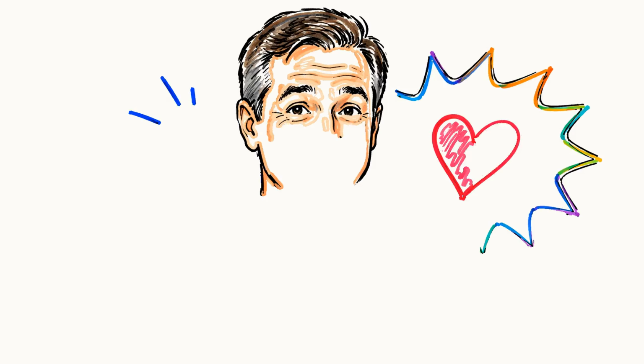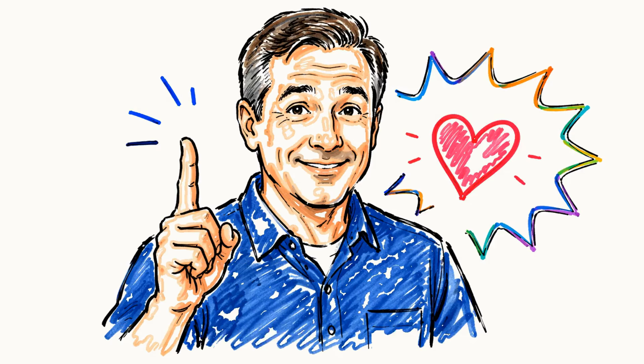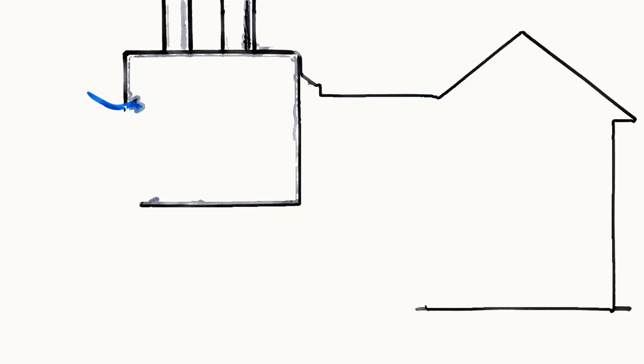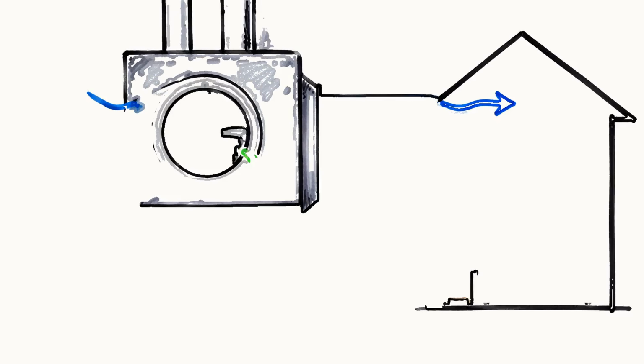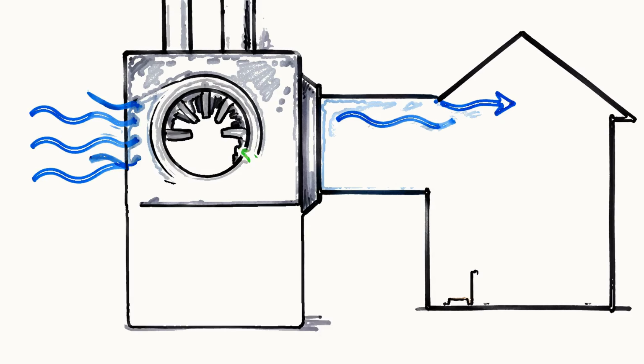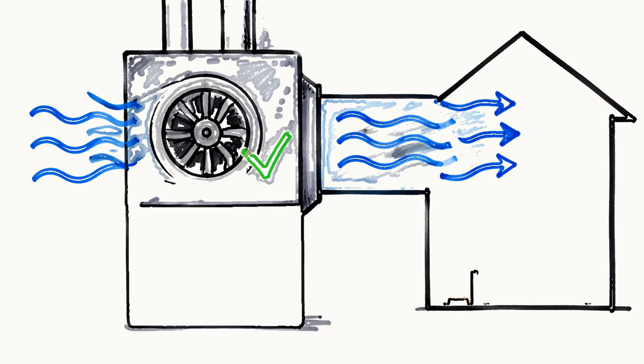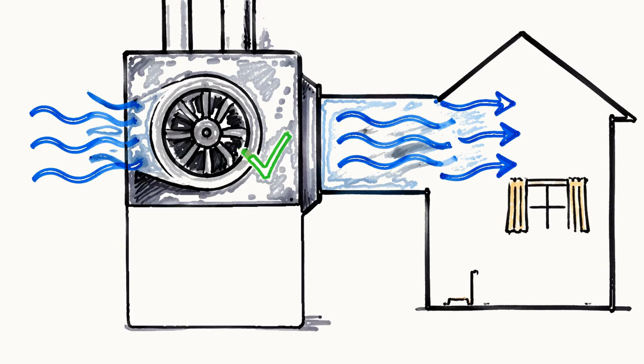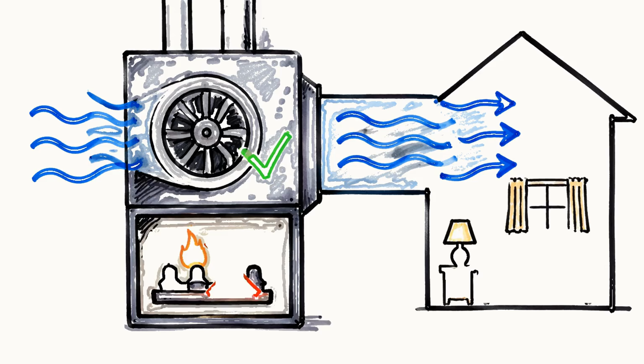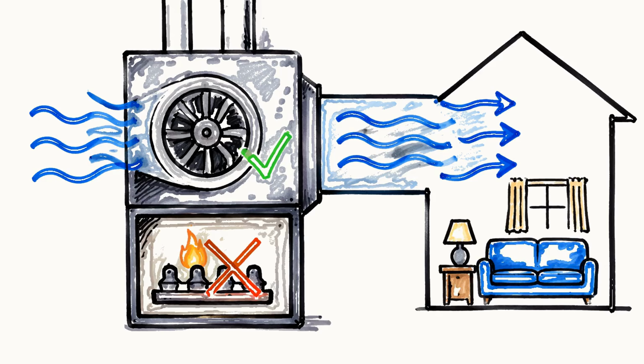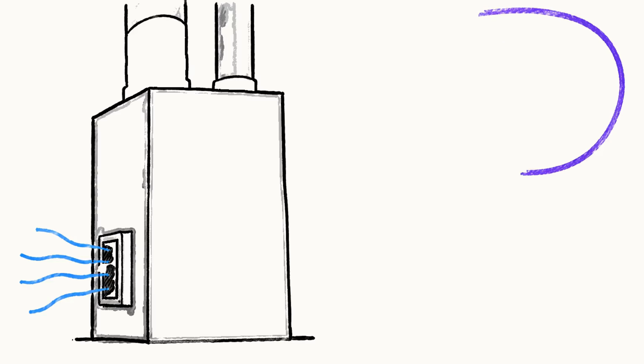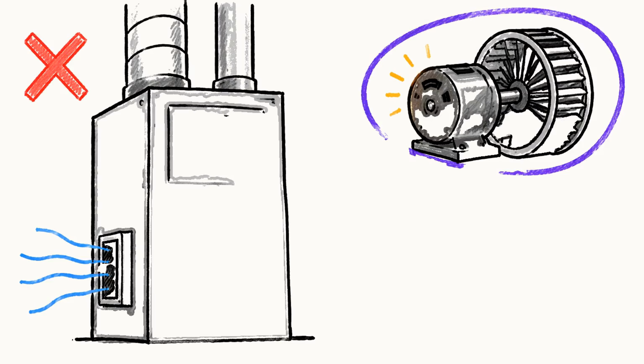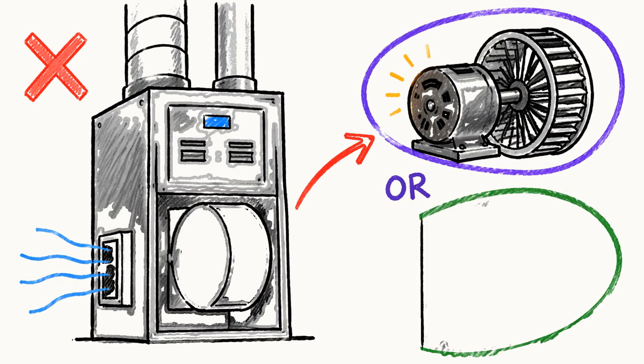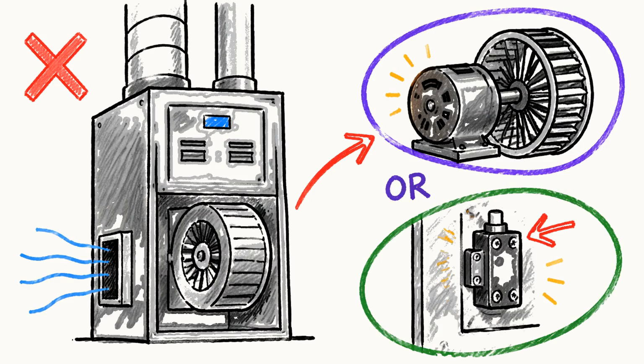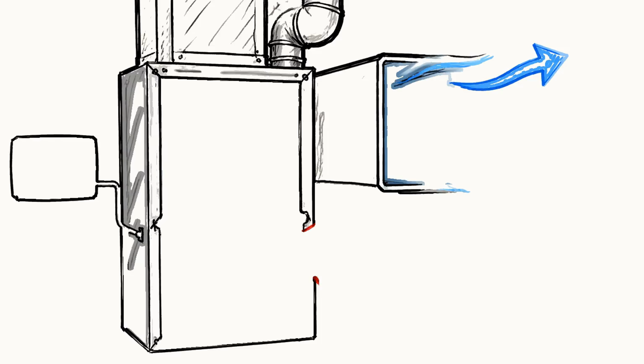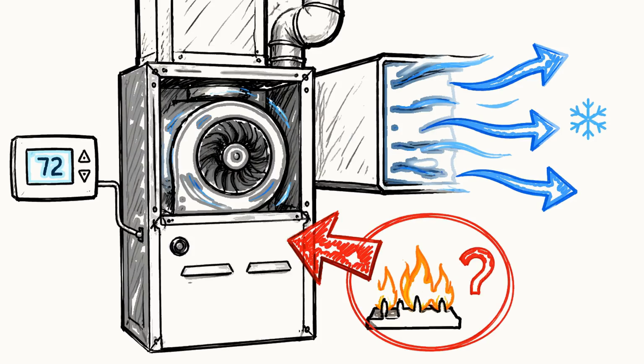Here is the part that should make you feel better before we even start. The fact that air is moving at all tells you the blower motor works, so this almost never means your whole furnace is dead. It means the heat side either never lit or lit and quit, and the fan is just pushing around the cold air that was already sitting in your ducts. If you are getting barely any air at all, that is a different lane, usually the blower itself or a safety door switch that is not seated, but cold air that is clearly moving points straight at the heat side.